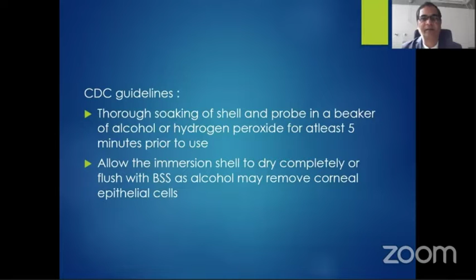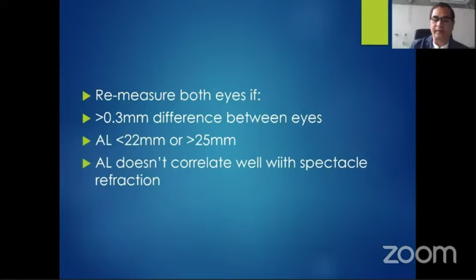Remeasure both eyes if the difference between the two eyes is more than 0.3 millimeter, if the axial length is smaller than 22 millimeters or larger than 25 millimeters, and if the axial length does not correlate with the spectacle refraction. Sources of error: axial length too short in cases if you have compressed the eye, if there is vitreous opacity, RD, thickening of RCS, or improper velocity setting.